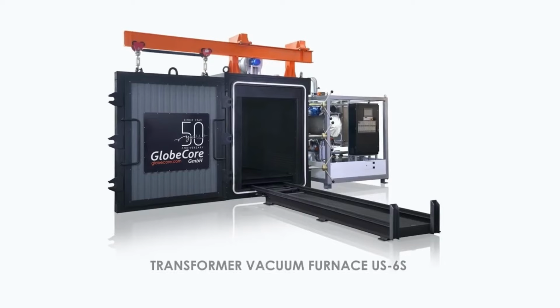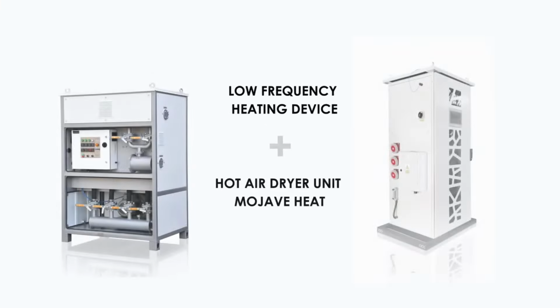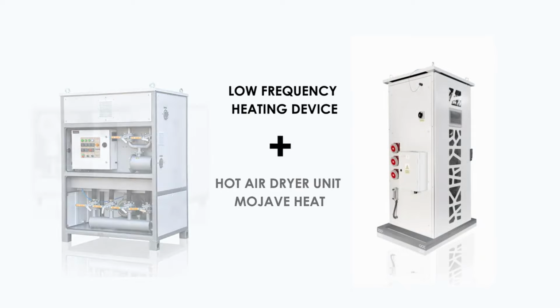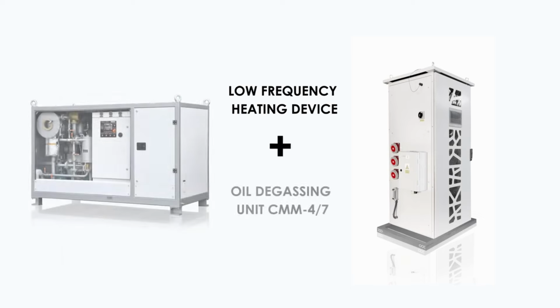Drying the insulation externally can be performed by heating and vacuum in the US vacuum oven. There are several equipment combinations to dry the transformer insulation without extracting the windings: low-frequency current and a Mojave heat hot air blower, low-frequency current and a CMM-4/7 unit to circulate oil inside the transformer, as well as low-frequency current combined with an INI vacuum cold trap unit.